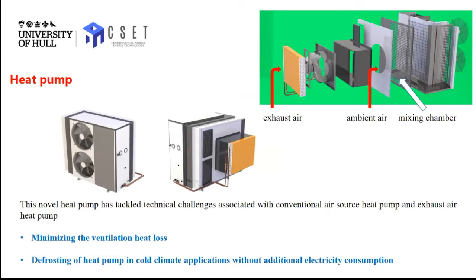So look at our heat pump. We got two evaporators. First, the evaporator is going to recover heat from exhaust air, meaning discharge air from the room space. Afterward, we got exhaust air mixed with ambient air. This mixed air is then delivered into the second evaporator for further heat recovery. In this way, we would be able to maximize use of ventilation air energy and minimize its energy loss. Most importantly, we can make use of exhaust air to defrost the heat pump instead of using electricity. We get rid of electricity for defrosting the heat pump, use ventilation air rather than electricity, and achieve significant energy saving in heat pump defrosting. So this is the structure of the heat pump.